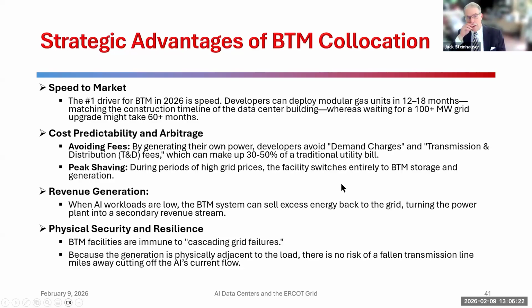Another thing is that if you generate your own power, you don't have to pay demand charges or transmission or distribution fees, and those can make up 30 to 50% of a traditional utility bill. Also, if you're purchasing power from the grid and have behind-the-meter generation and storage, you can play a game in Texas: knowing grid rates typically double in the evening, you can shut down your grid access, turn on the battery, and avoid those high cost periods.